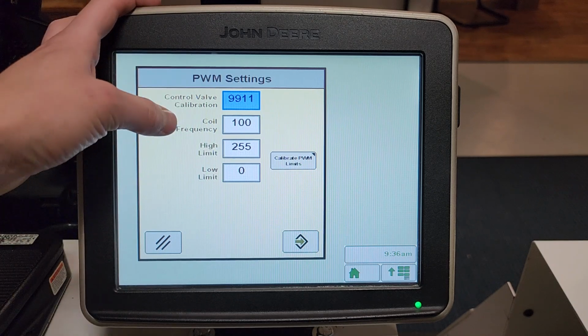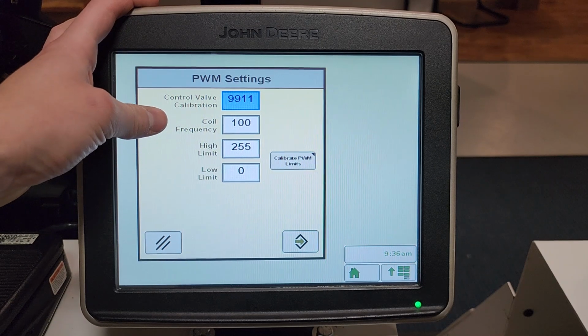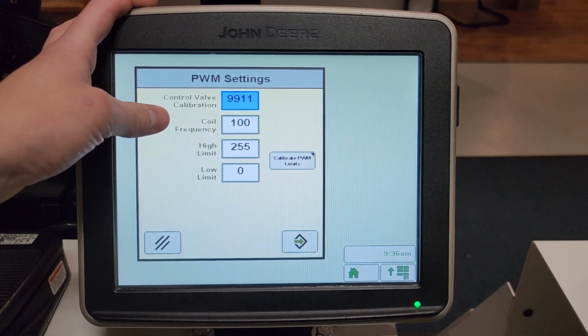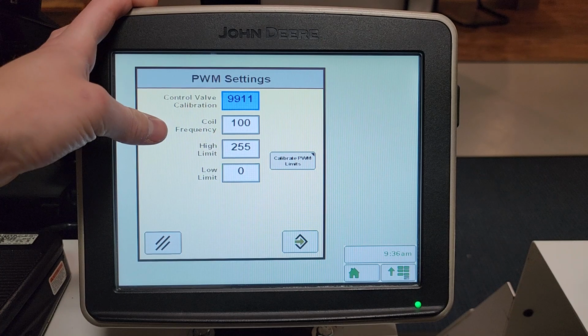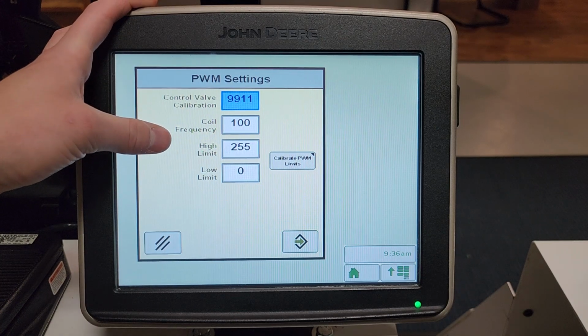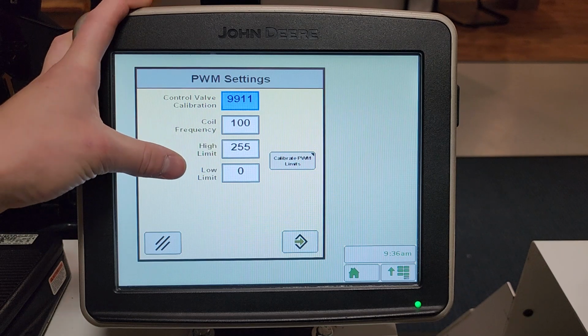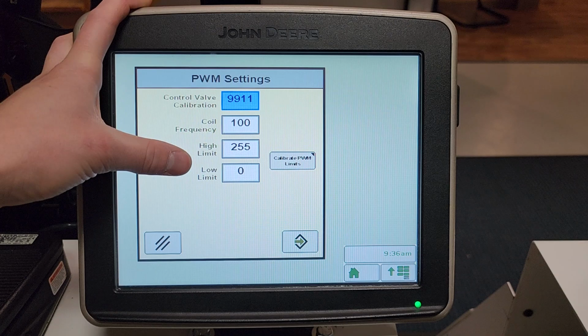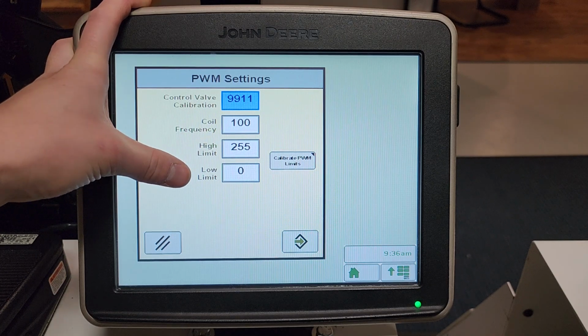Next will be your coil frequency for both the GX2 electric pump and the GX5 hydraulic pumps. This will be set at 100. Your high limit for both the GX2 and GX5 pumps will be 255. And then your low limit for the GX2 series of pumps will be 0, and then your low limit for the GX5 hydraulic series of pumps will be 60. So say with the GX5, if you can't get to a low enough rate, then you can drop that low limit down to say 30 or whatever number you think is best.